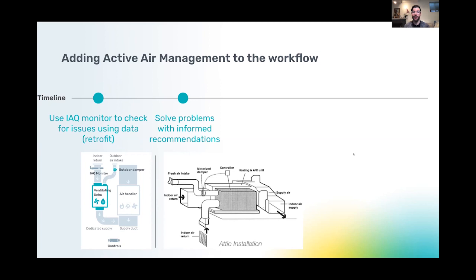Now that air will be hot because it's been reheated and because it's come from outside. And so you're dumping hot air into a cold supply duct right after the air conditioner. And so you do need space for mixing. The air needs to mix properly before it gets distributed. So the one issue with this installation is if you do it improperly, the hot air will unevenly affect a room in the home because it's getting sucked into one supply branch. And now that cold room becomes hot because it's getting dumped all this hot air. So you do want a couple of feet, ideally 3 feet of mixing before you start getting any branches off to the supply side.